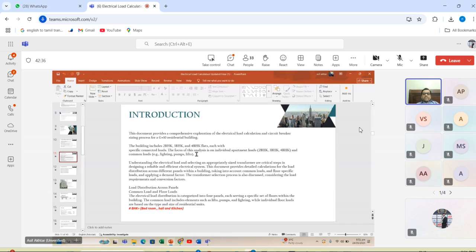The focus of this analysis is on the individual apartment loads, 2 BHK, 3 BHK, and 4 BHK, and common loads, including lighting, pumps, and lifts. Understanding the electrical load and selecting an appropriate size transformer are critical steps in designing a reliable and efficient electrical system. This document provides detailed calculation for the load distribution across different panels within a building, taking into account common loads and floor specific load and applying a demand factor. The transformer selection process is also discussed, considering the load requirement and conversion factor.